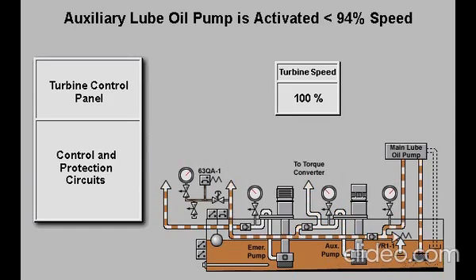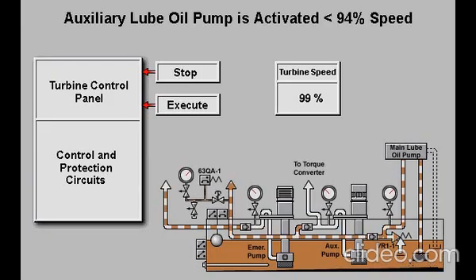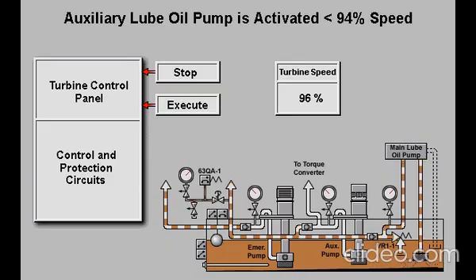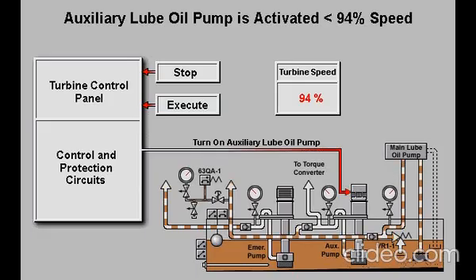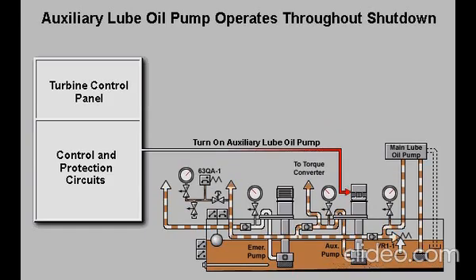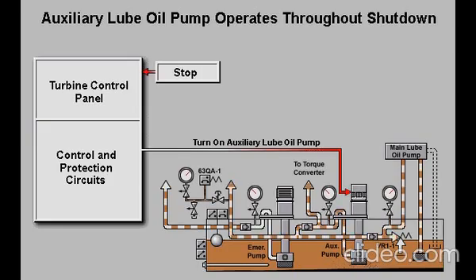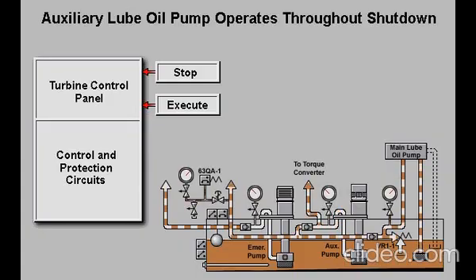Normally, turbine shutdown is initiated when the lead operator selects stop and execute on the operator interface of the turbine control panel. The turbine may also shut down automatically when the control and protection systems detect an unsafe operating condition. In either case, the control system will turn on the auxiliary lube oil pump when the turbine speed drops below 94% of operational speed. The auxiliary lube oil pump operates throughout the shutdown and cool-down periods and is shut off when the lead operator selects stop and execute once more.